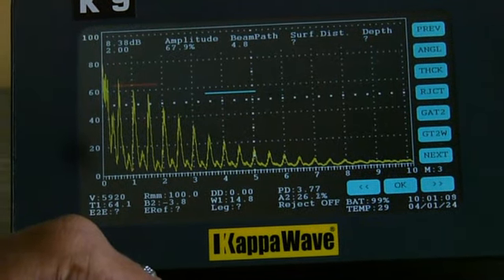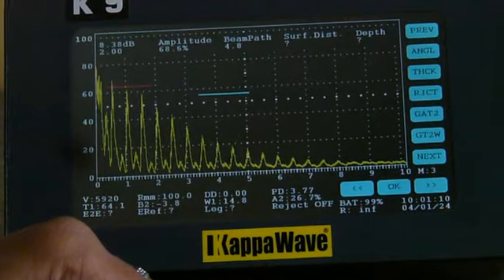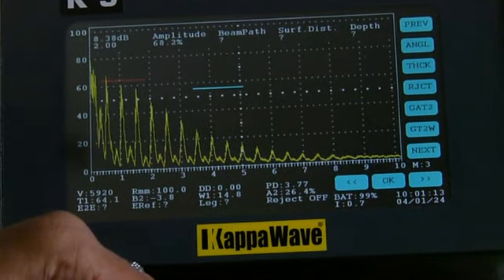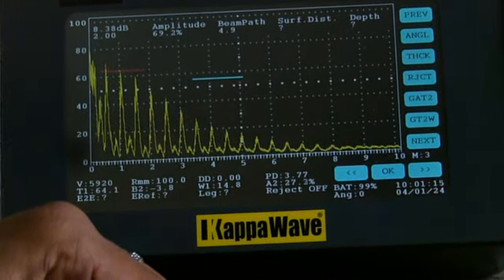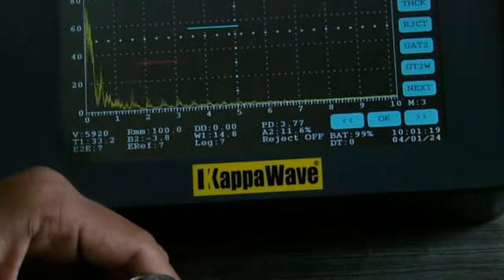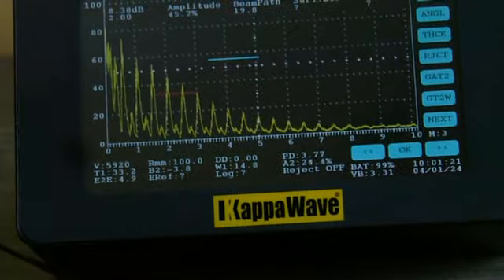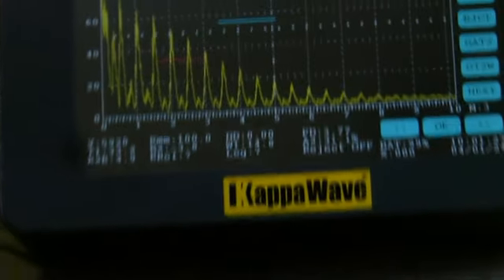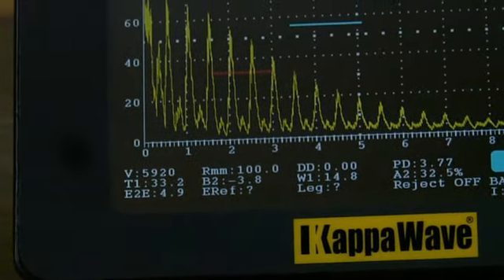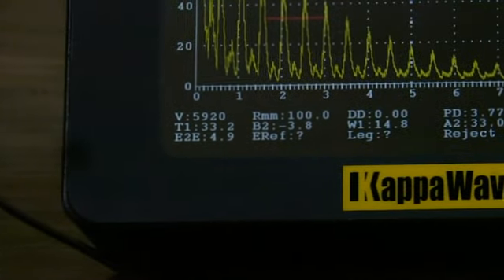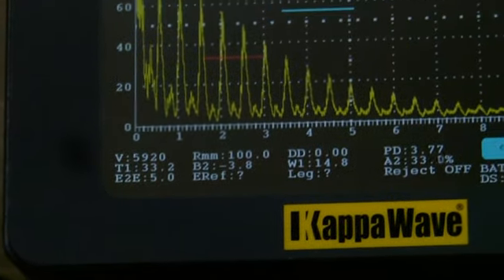If the first echo happens to be within the dead zone and is not readable, then you may extend the gate to cross any two indications. That way it will give you the echo to echo value. Now this technique may also be used to measure the thickness of a coated material.